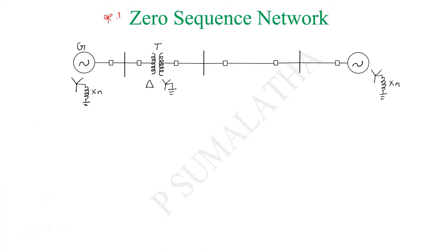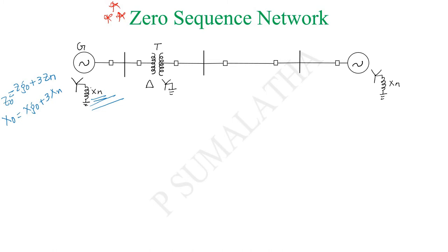For the zero sequence network concept, you need to understand how to represent it with respect to different transformer winding connections. The zero sequence component of the generator is represented as Z0 = ZG0 + 3ZN, or in terms of reactance: X0 = XG0 + 3XN. Here they have given the value of XN, so we represent it in the zero sequence network. For negative and zero sequence, there is no EMF. This is the XG0 value and this is 3XN — this is the generator equivalent circuit.